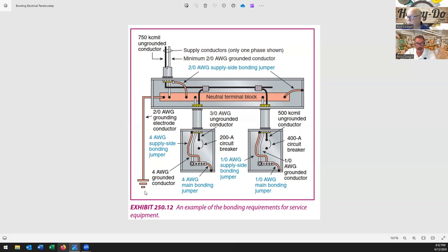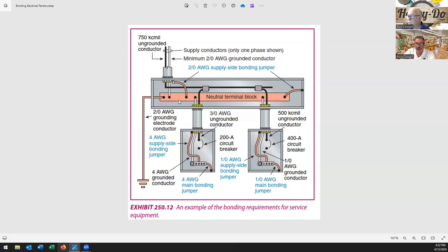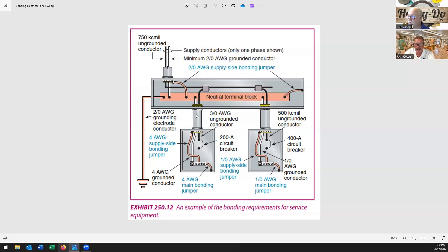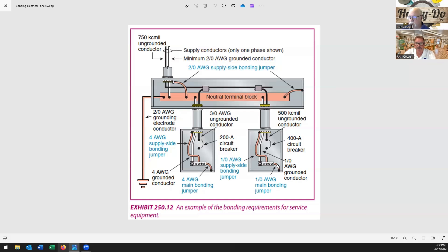So this one we're showing where we have our ground over there in the bottom left and then that goes to your neutral terminal block. But you can see the bond jumper in the case way all the way to the right and to the left - there's where you're bonding. So now that case is going to carry the same - they do the same thing when they get into the sub panels. They put another bond on there so if I was to touch the case or the panel below, the boxes are going to be exactly the same. I'm not going to have a difference in potential.